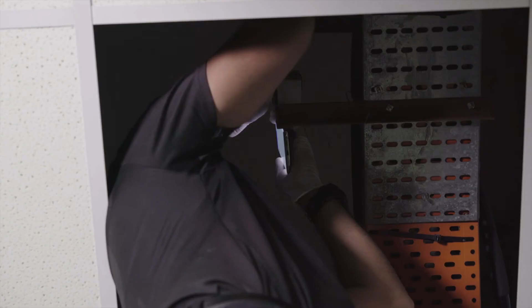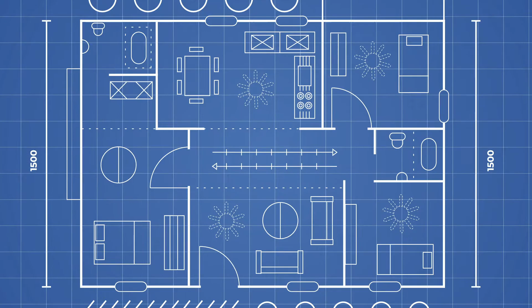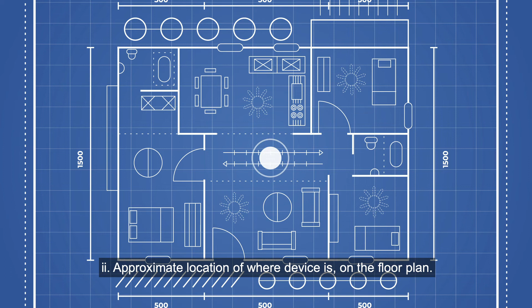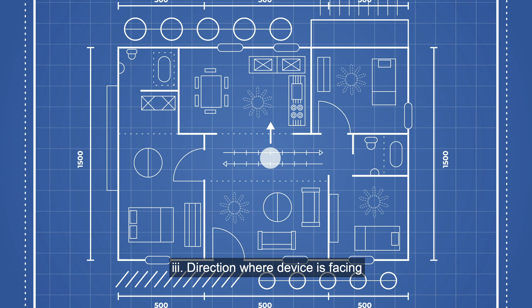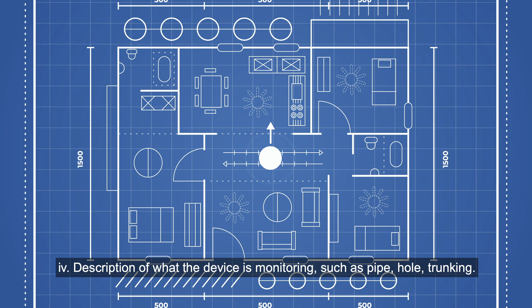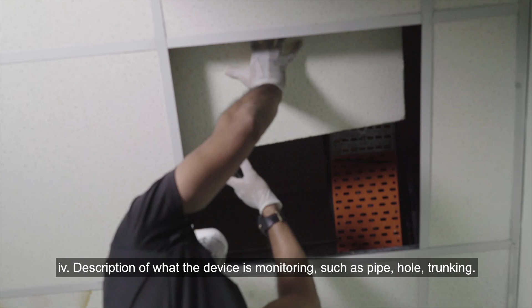During or after securing the device in position, please take note of the following: device serial number, approximate location of where the device is on the floor plan, direction where the device is facing, and a description of what the device is monitoring, such as pipe, hole, trunking.